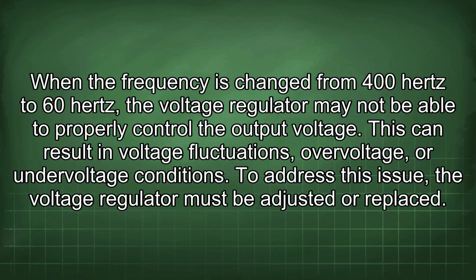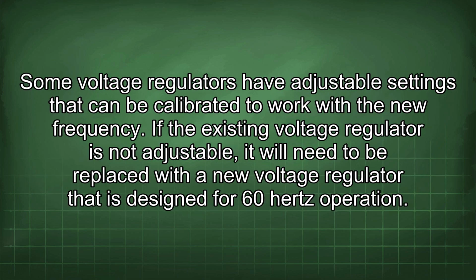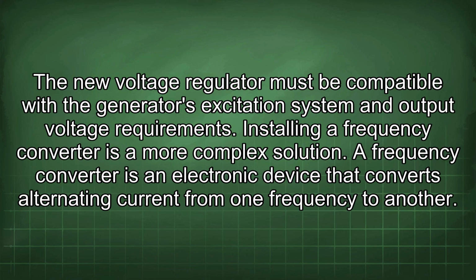When the frequency is changed from 400 Hz to 60 Hz, the voltage regulator may not be able to properly control the output voltage. This can result in voltage fluctuations, overvoltage, or undervoltage conditions. To address this issue, the voltage regulator must be adjusted or replaced. Some voltage regulators have adjustable settings that can be calibrated to work with the new frequency. If the existing voltage regulator is not adjustable, it will need to be replaced with a new voltage regulator that is designed for 60 Hz operation. The new voltage regulator must be compatible with the generator's excitation system and output voltage requirements.